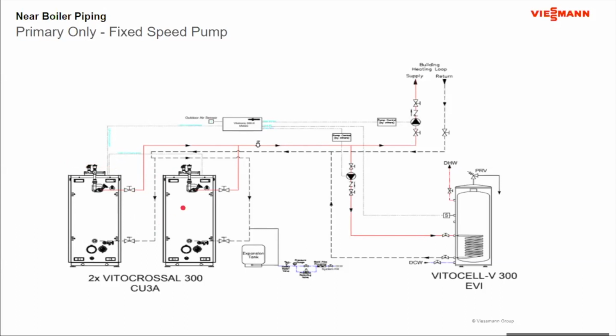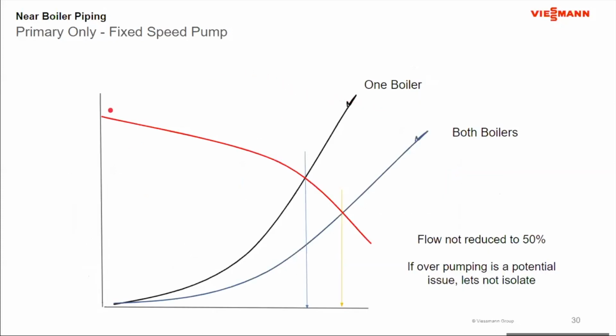The other reason this comes into play is that generally in this kind of installation there is no variable speed pump. So no ECM motor on the pump, no VFD. I have a fixed speed pump moving a fixed volume of water, regardless of whether 1 boiler or 2 boilers are operating. We also tend to see this with boilers that have a low pressure drop. With that fixed speed pump, it brings in a couple of unique problems. If I'm only running 50% of load, I would just like to run 1 boiler and isolate the other.